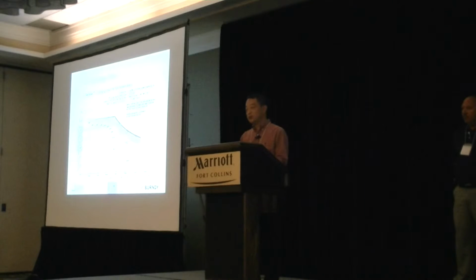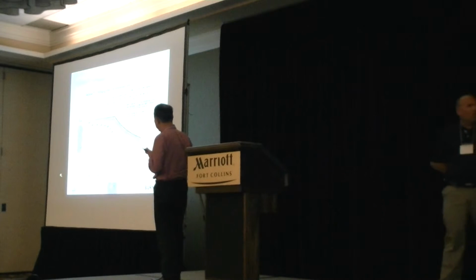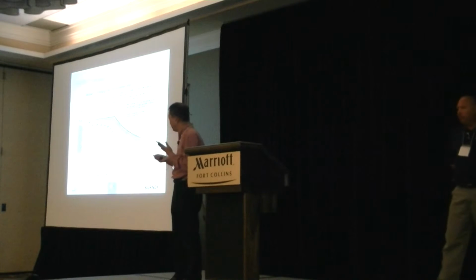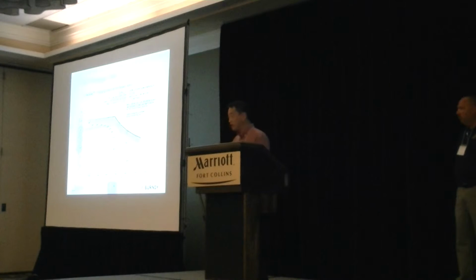We basically wanted to validate the strain curves that the Implo provided to us. If you look here, there are 2 axes. This is the strain curve that we got. This is line angle, and this is conductor tension. So this chart basically tells us what line angles are acceptable for any given tension. We really wanted to validate this for the TRTP project.